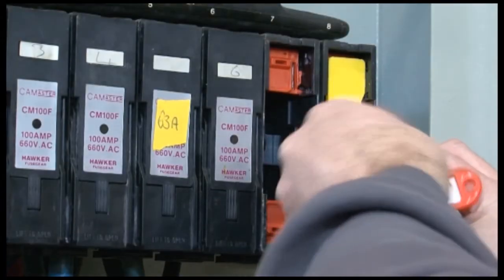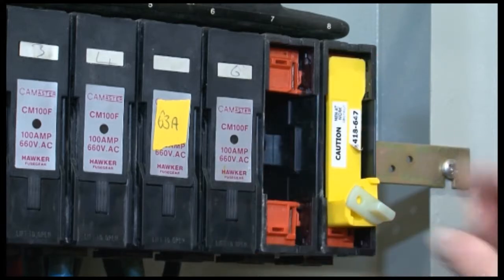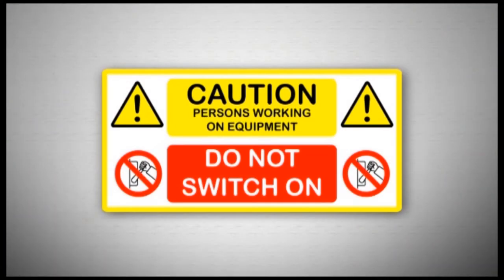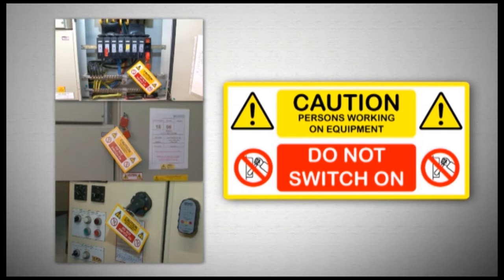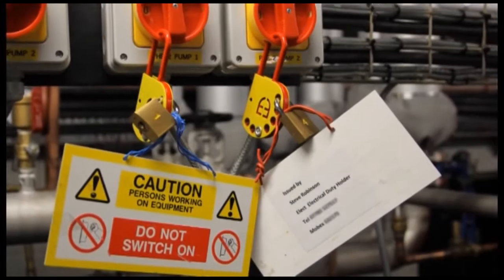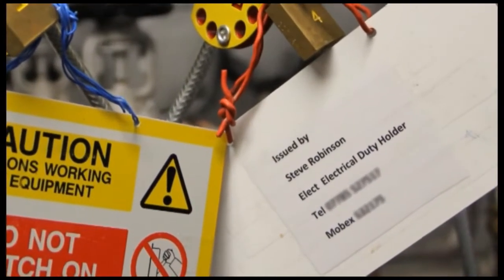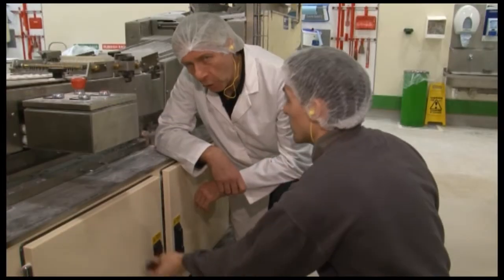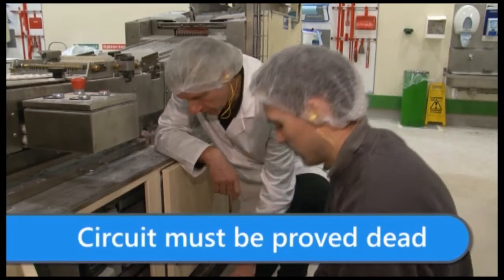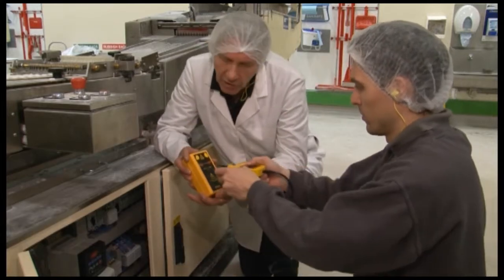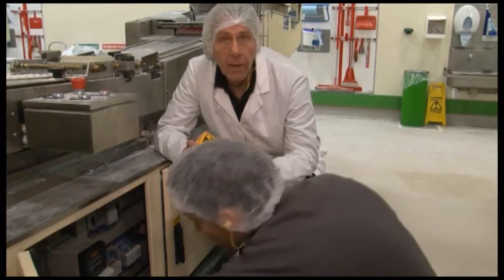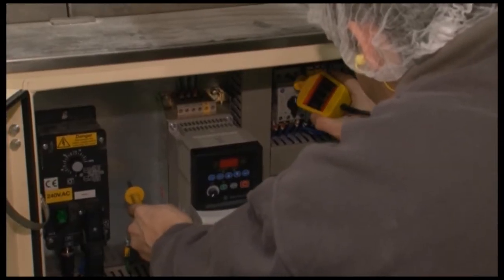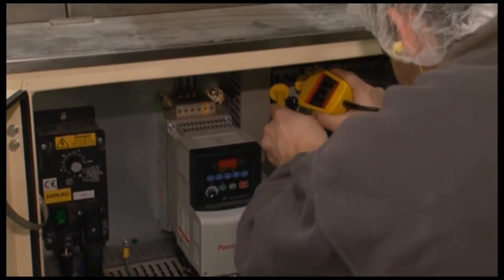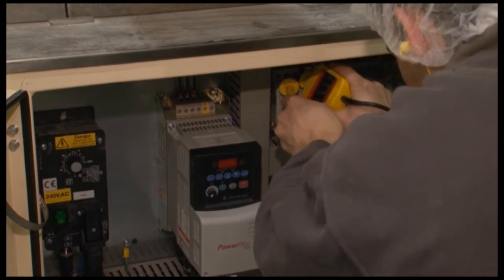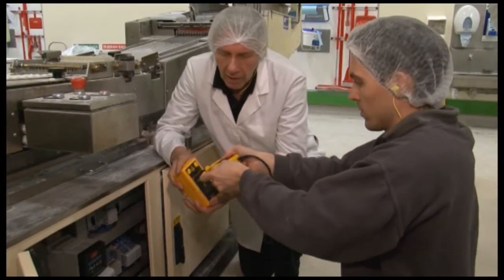Keys used for locking off, and also any fuses removed, must remain under the control of the person carrying out the work whilst they're working on the equipment. Caution signs must also be posted at all points of isolation. And a means of identifying the person who carried out the isolation is useful, so they can be traced if necessary. Lastly, and most importantly, before starting work, the circuit must be proved dead. To do this, first check your voltage indicator, then check for dead, and then check your voltage indicator again.